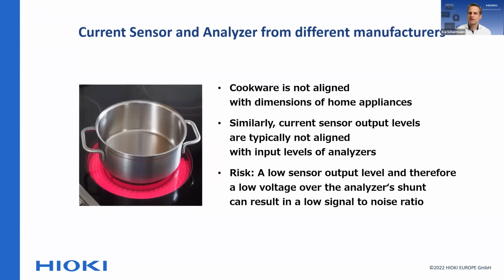Current sensor output levels are typically not aligned with the input levels of analyzers, because current sensors are typically made by different companies than those who make the power analyzers or measurement devices. Hioki is actually the exception to that. But if you have a current sensor and an analyzer from different manufacturers, there's a risk that a low sensor output level will result in a low signal-to-noise ratio, which has a negative impact on your measurement. So that's really something to look out for.